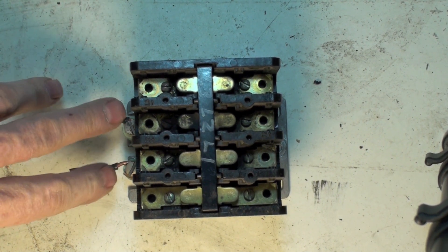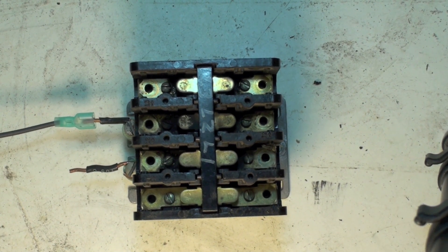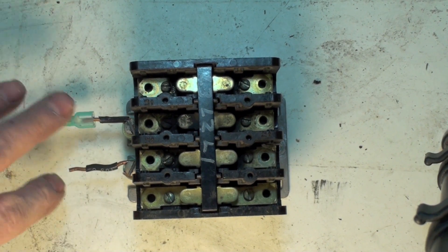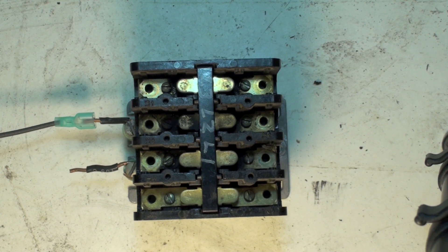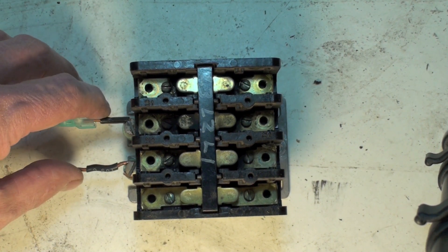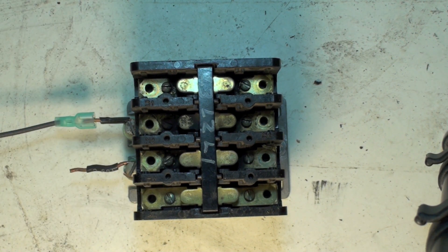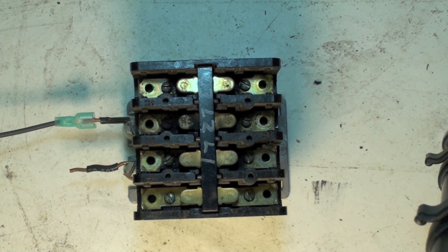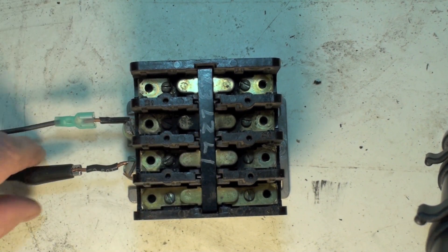If there is low voltage in here, then you have to check voltage while it's operating. You know, energize this and then check right across here. Don't check at the source or anything like that without this energized. You'll have to have power to it for the voltage drop to show. So in this case, this is low voltage, and that's the effects of low voltage and armature wear.